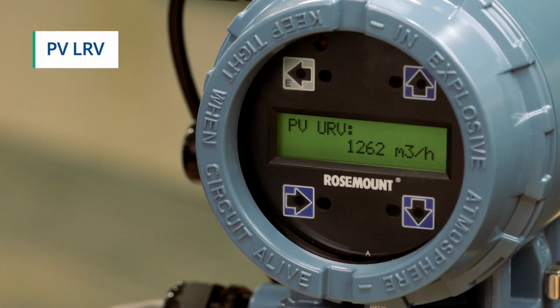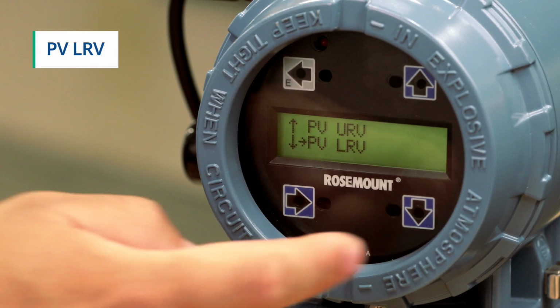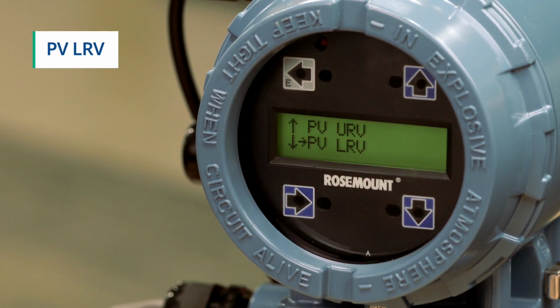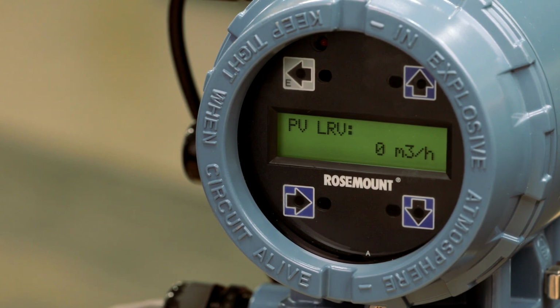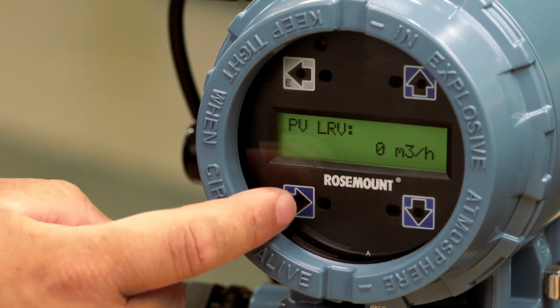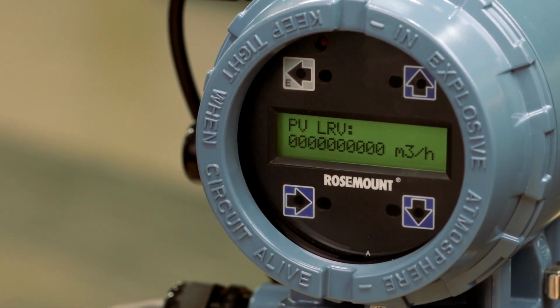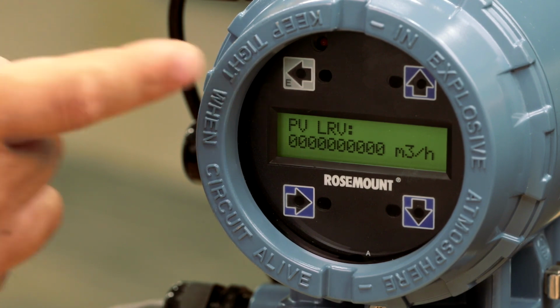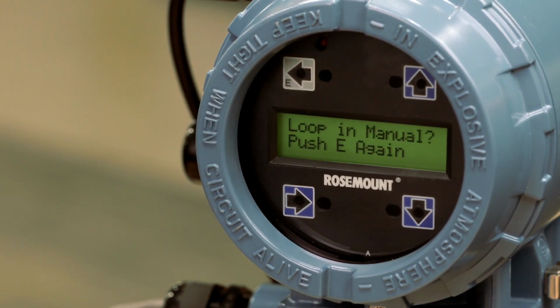To complete the analog output range, set the primary variable lower range value, or PV-LRV. To start, press the E button to navigate back to the basic setup screen. Press the down arrow to scroll through the menu options, and press the right arrow to select PV-LRV. Then press the right arrow to move the cursor to the place value that needs to be changed, and press the up and down arrows to increase or decrease the value. When the PV-LRV value is entered properly, press the E button to select the value. Finally, press the E button again to save your selection.